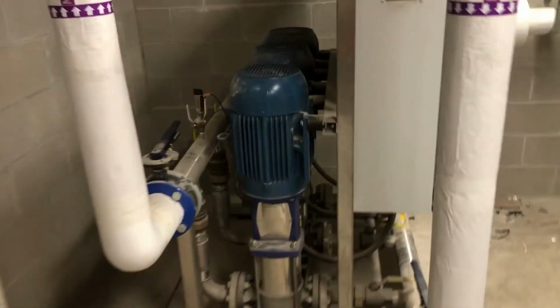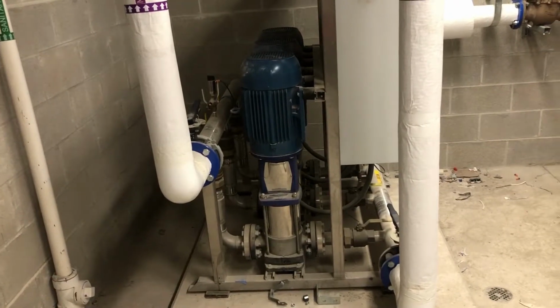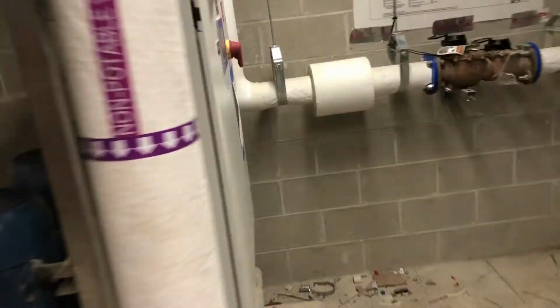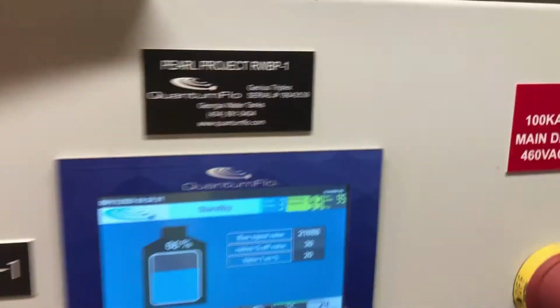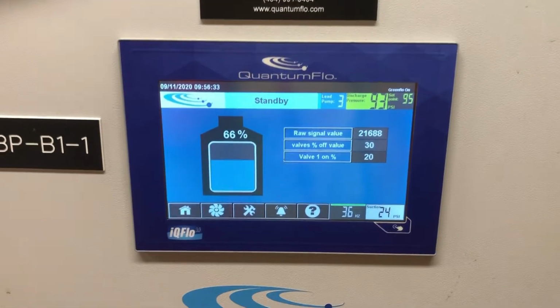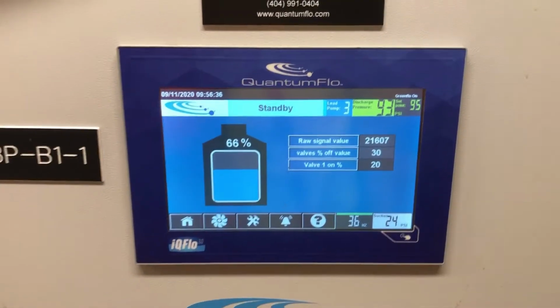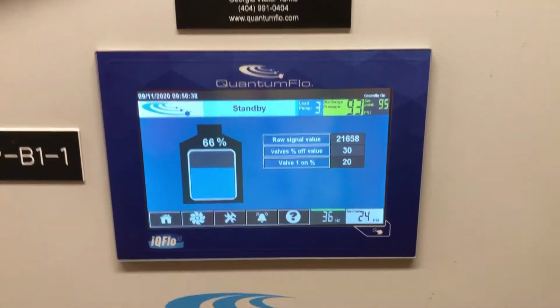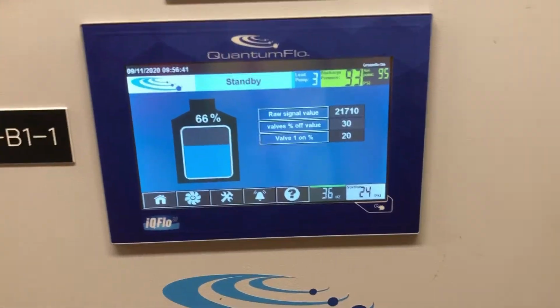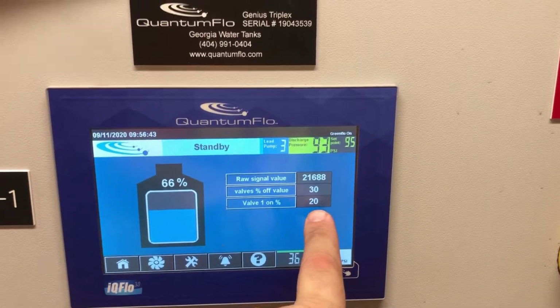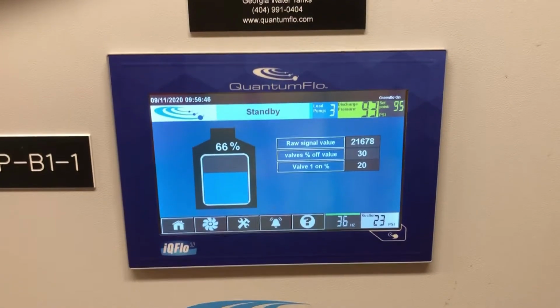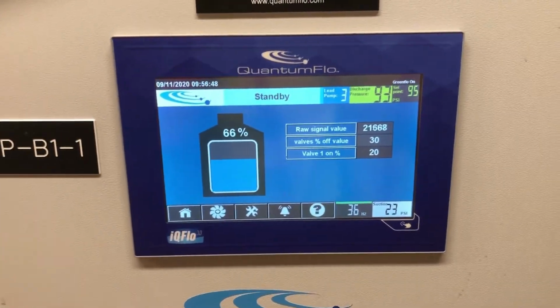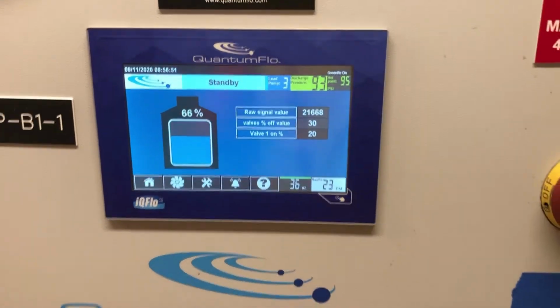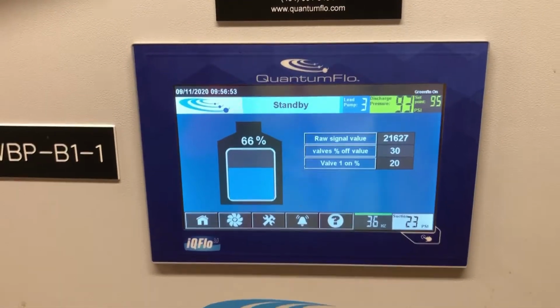Building pumps. This is the NPW pump. It looks like a regular domestic water booster because it pretty much is. It works based on drop in discharge pressure. Right now we have 93 psi on the discharge side. The only difference is this tank control, which is used for other things too, but it works great for rainwater harvesting. So right now this tank level is set to open at 20% and close at 30%. Eventually we'll have it closing at 90 or 95%, and we can start it lower than that or higher. It doesn't really matter.